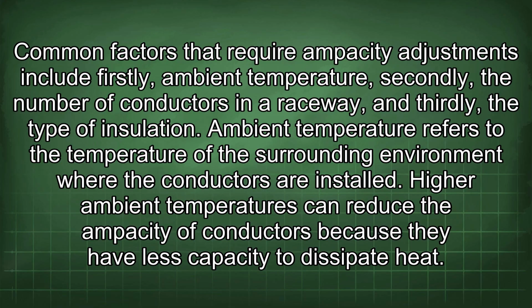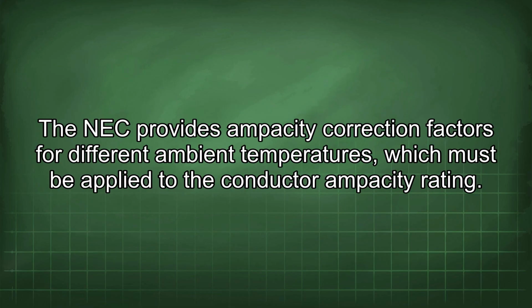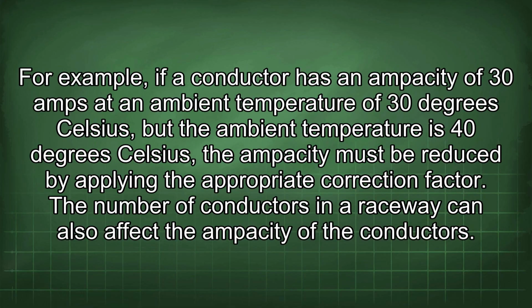the type of insulation. Ambient temperature refers to the temperature of the surrounding environment where the conductors are installed. Higher ambient temperatures can reduce the ampacity of conductors because they have less capacity to dissipate heat. The NEC provides ampacity correction factors for different ambient temperatures, which must be applied to the conductor ampacity rating. For example, if a conductor has an ampacity of 30 amps at an ambient temperature of 30 degrees Celsius, but the ambient temperature is 40 degrees Celsius, the ampacity must be reduced by applying the appropriate correction factor.